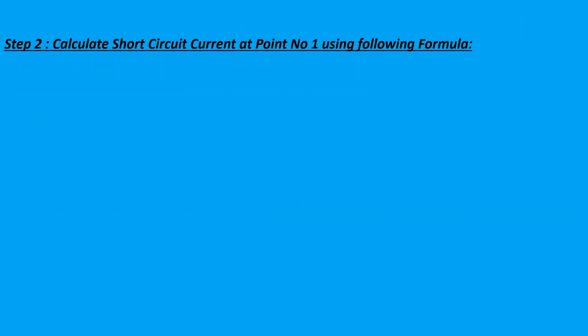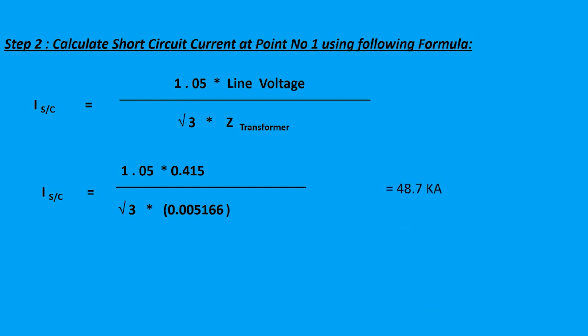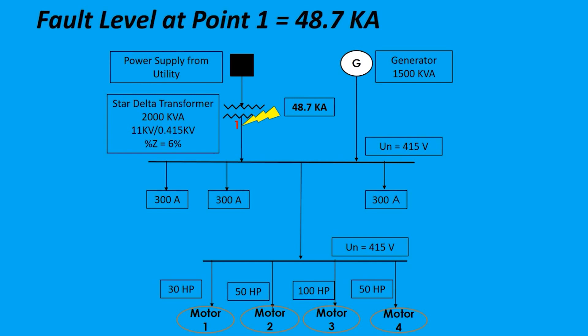Step two: calculate the short circuit current at point number one using the formula — short circuit current equals 1.05 times the line voltage, divided by root 3 times Z transformer. Therefore, ISC equals 1.05 times 0.415, all divided by root 3 times 0.005166, so ISC equals 48.7 kilo amperes. The fault level at point one is 48.7 kilo amperes.